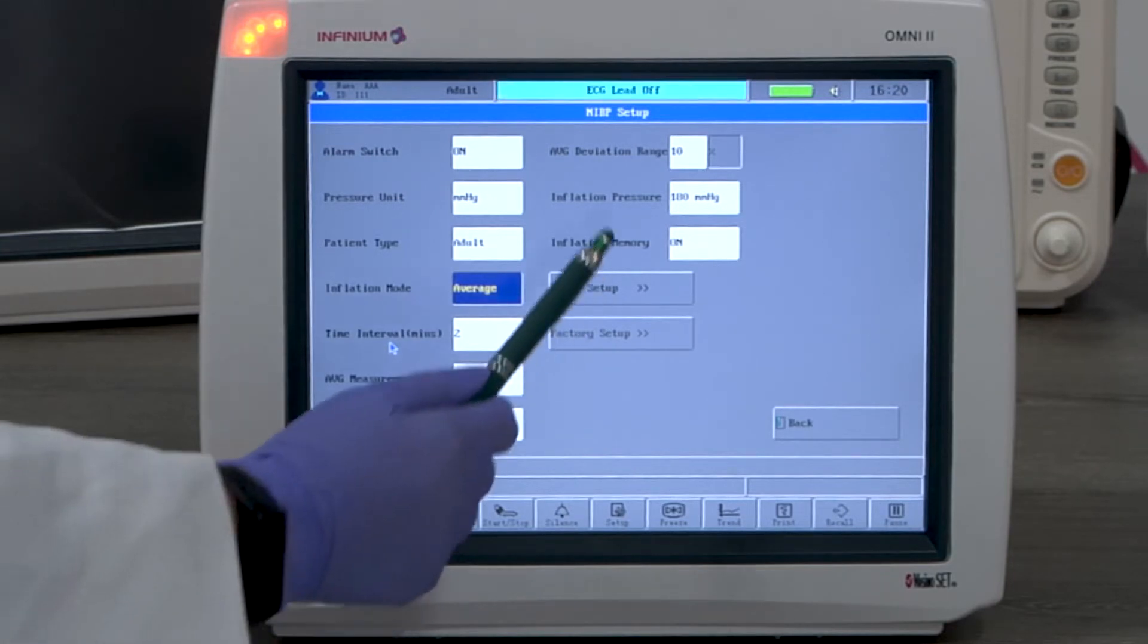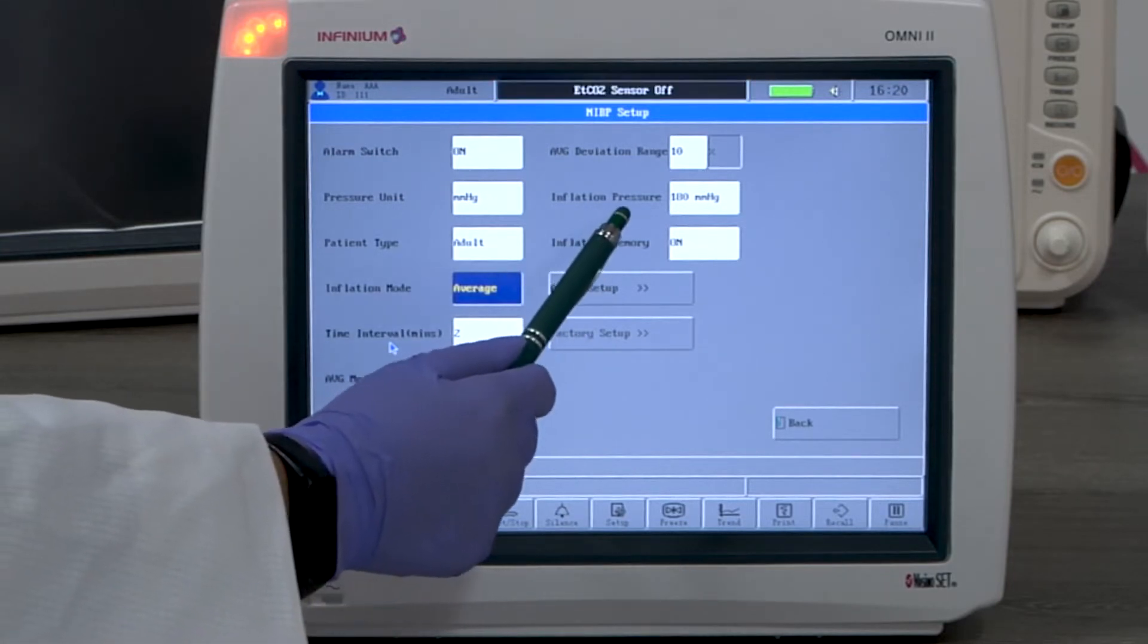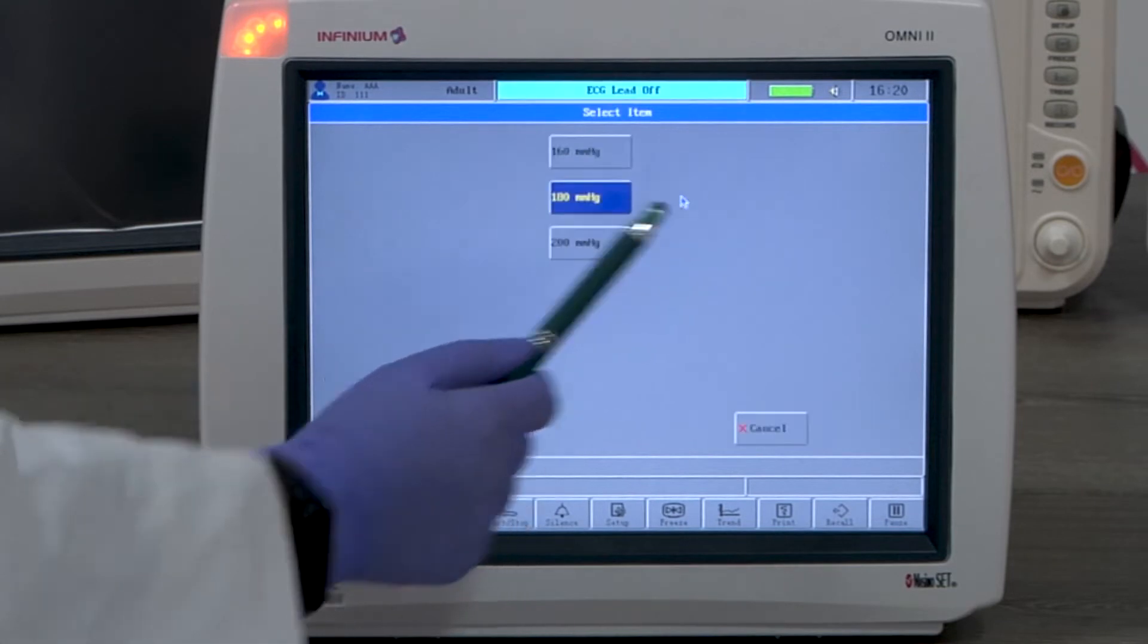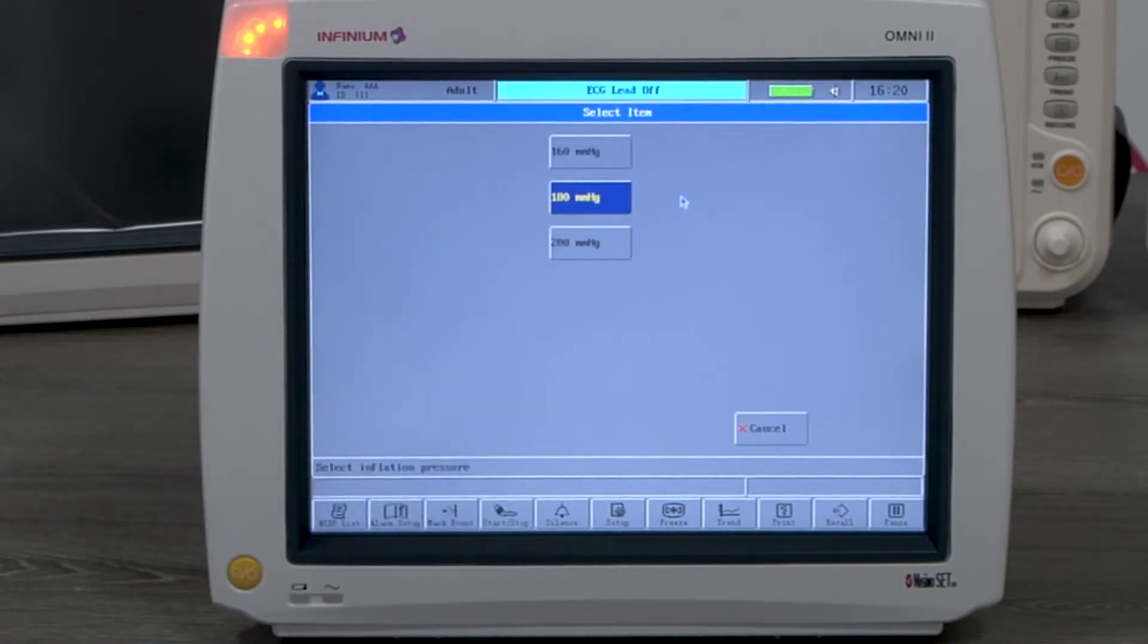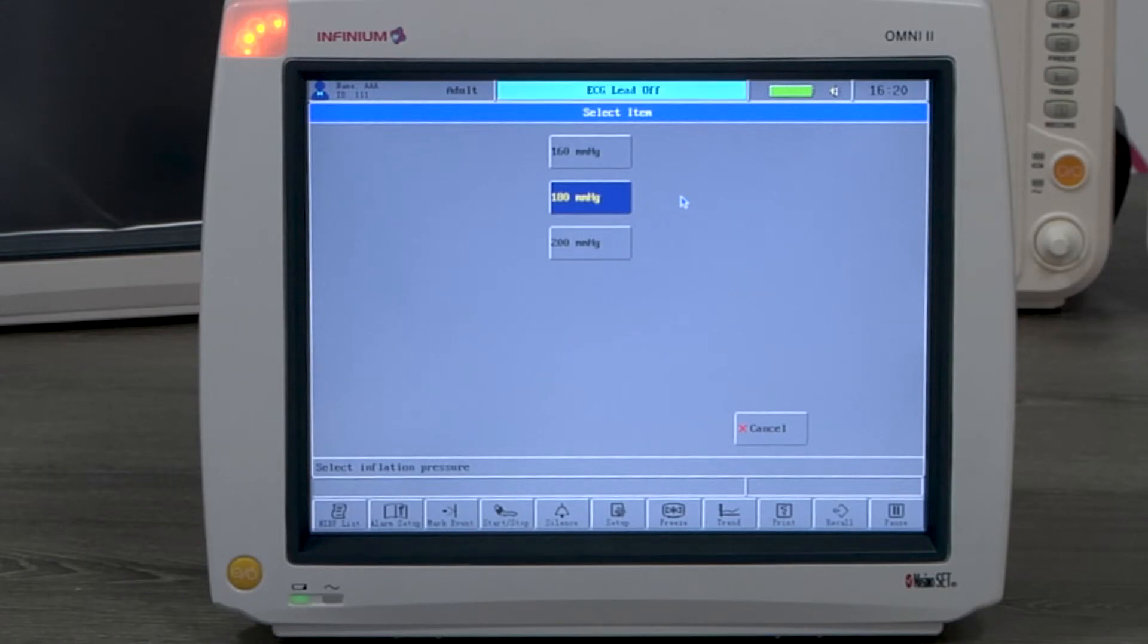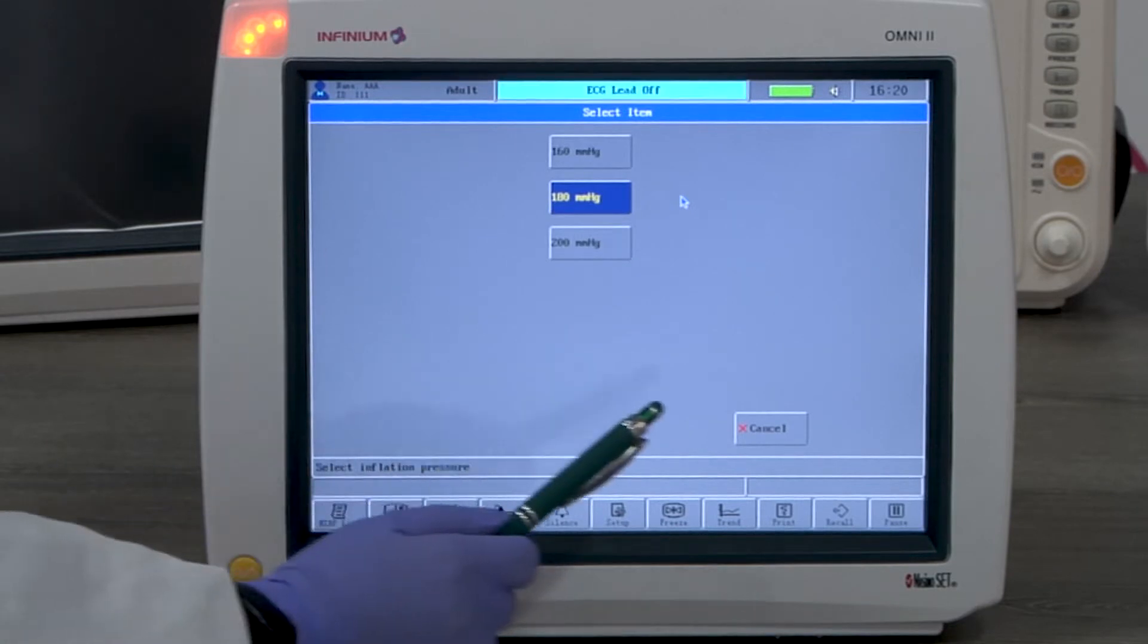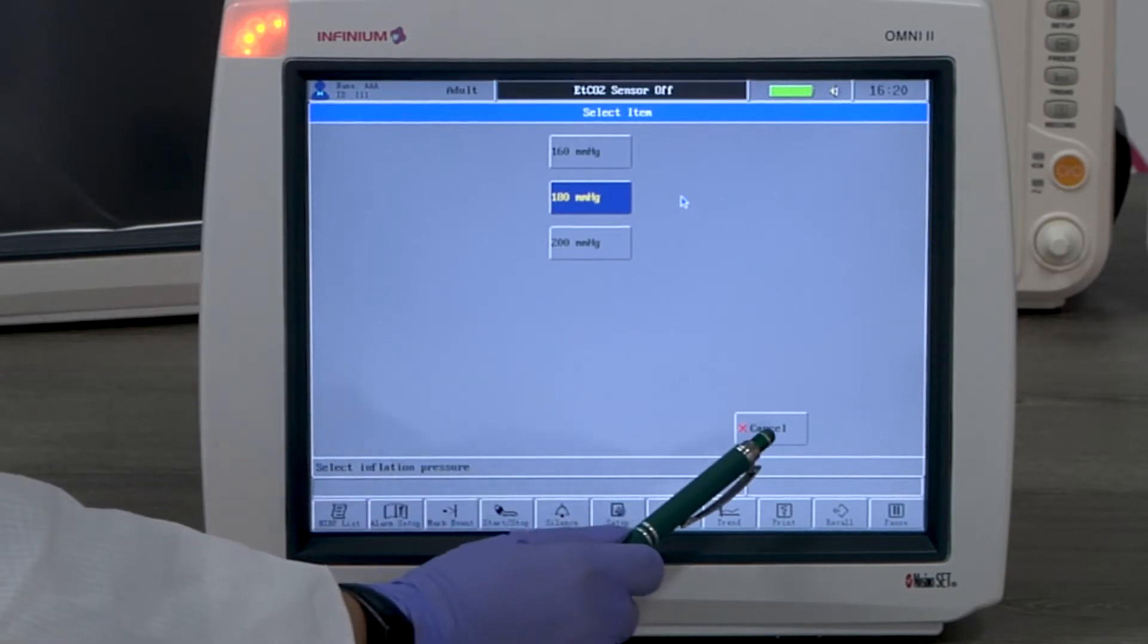The inflation pressure is the initial inflation pressure. The default is 180 and it can be set to a lower or a higher value depending on which one fits better in the clinical use.